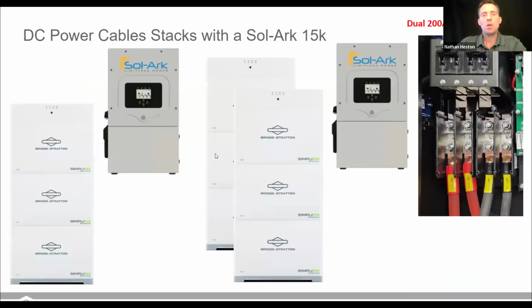If you're doing an installation, just a quick word on cabling with a Sol-Ark 15K. So a Sol-Ark 15K has dual DC inputs for the batteries, dual set of breakers there, and you want to make sure that you're landing on both of those breakers. So even if you're doing a single stack, we recommend double-lugged 1-aught battery cables, so 2 reds, 2 blacks, coming from a single stack going into each of those inputs on the Sol-Ark. And then if you're doing 2 stacks, obviously you would do 2 sets of battery cables, 1 from each stack. And you can use that Sol-Ark 15K battery input as your combiner. So that's a nice feature of the 15K, having those dual inputs and those dual breakers there, as you don't need a battery combiner, again, simplifying your installation.